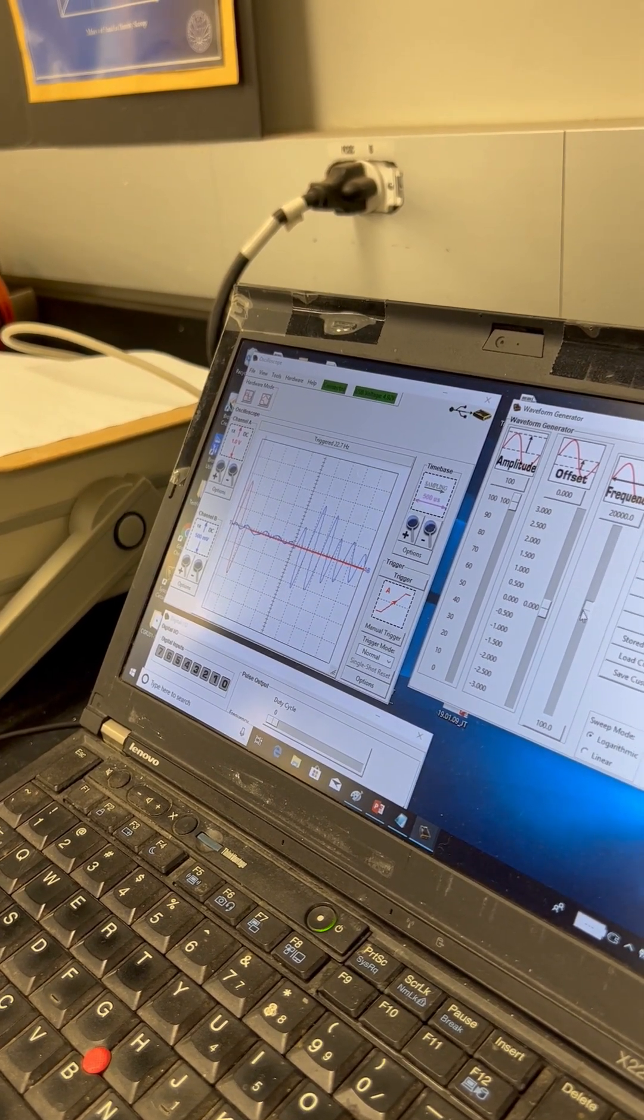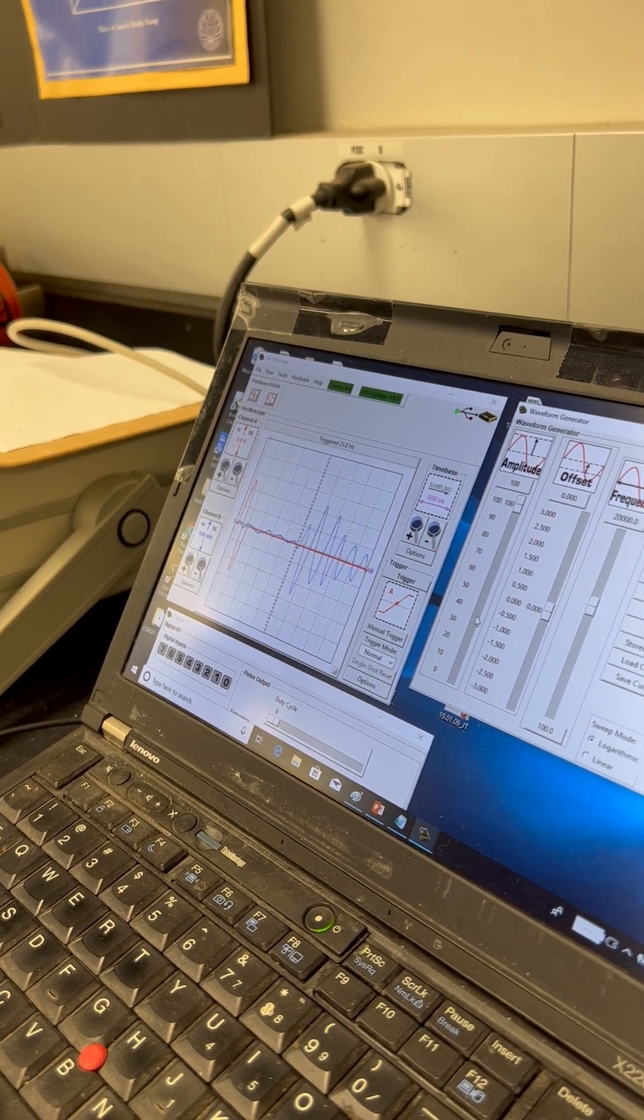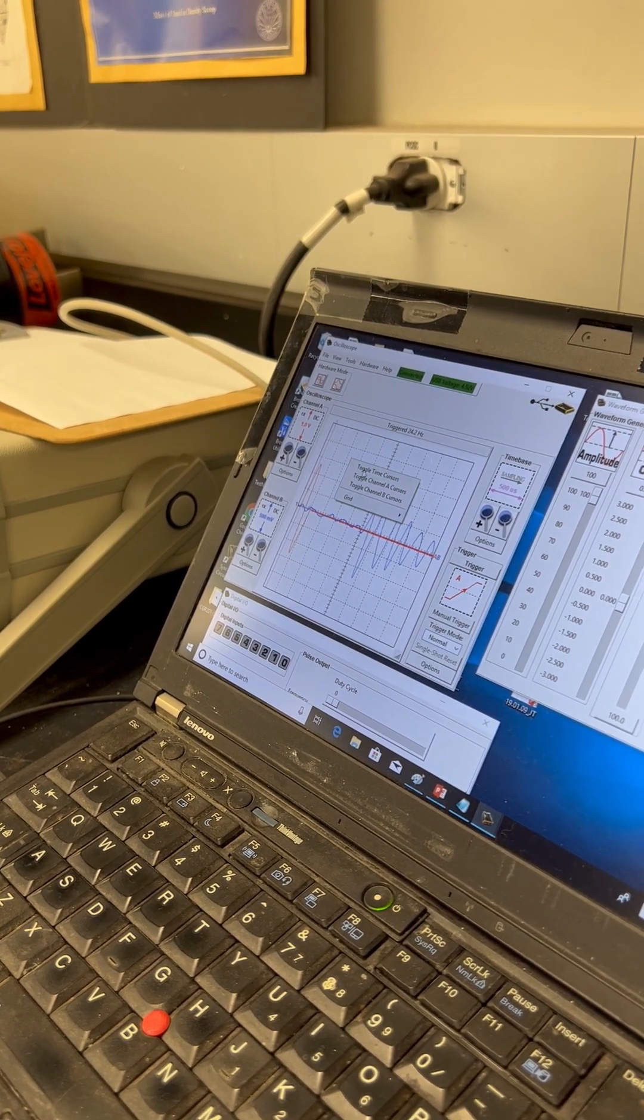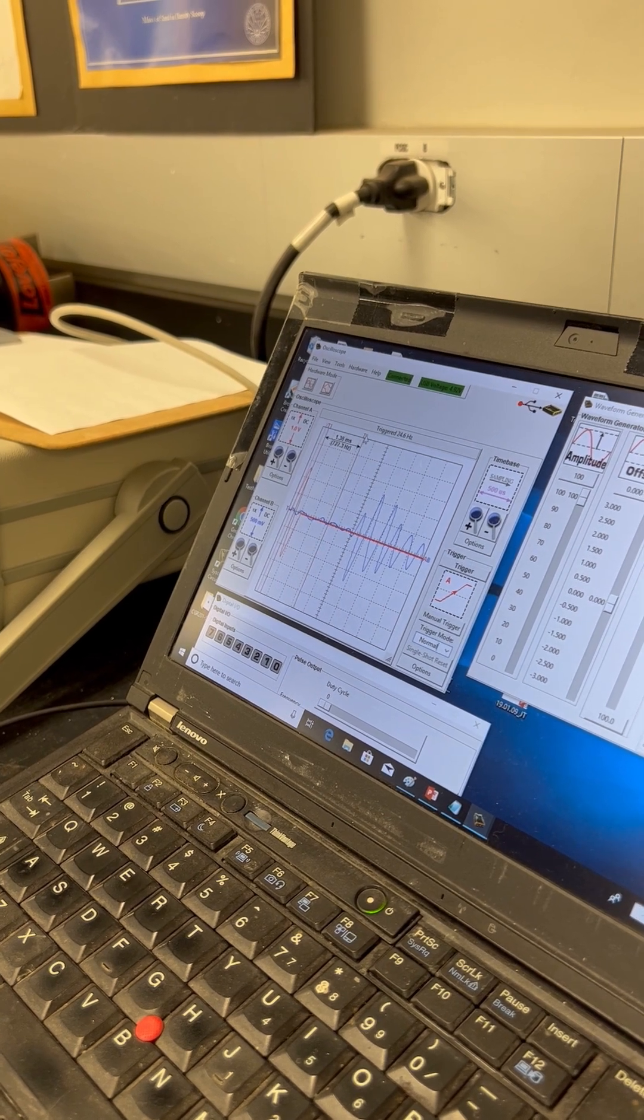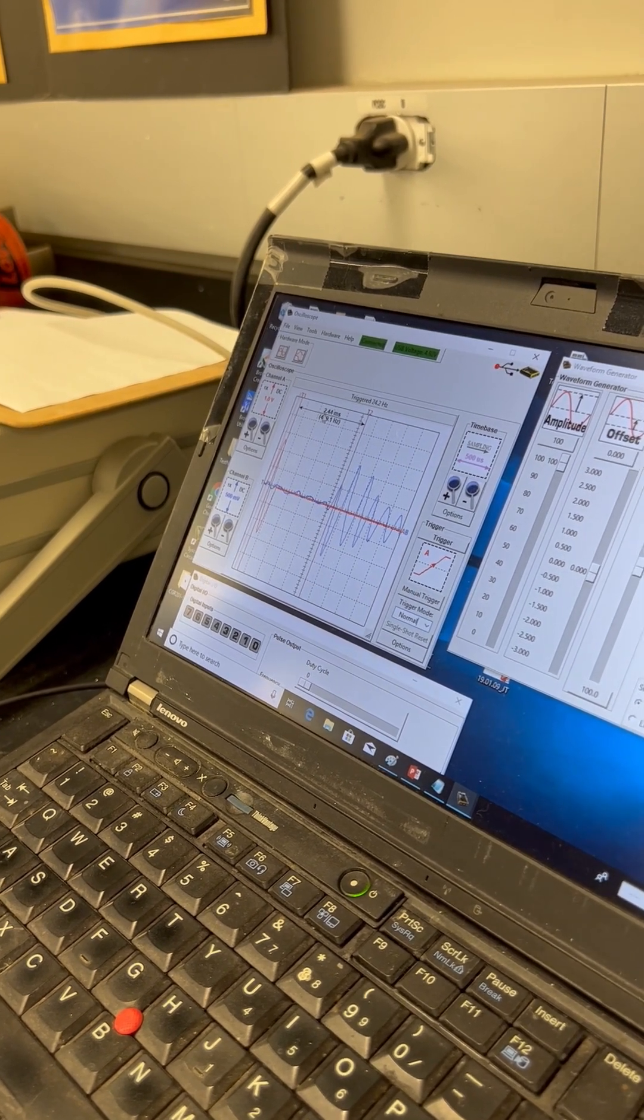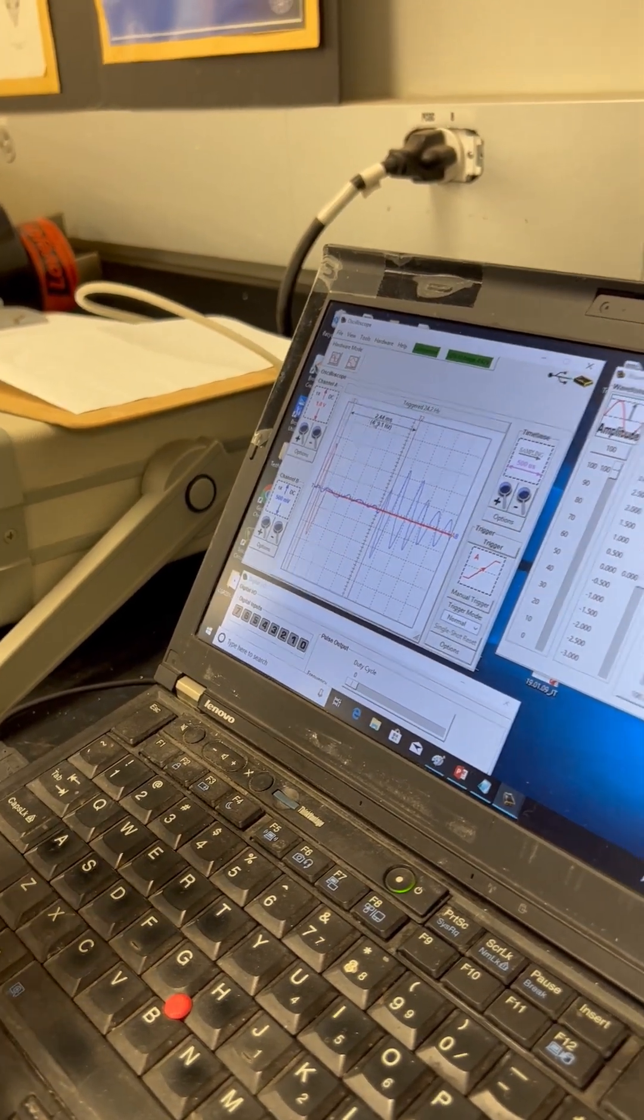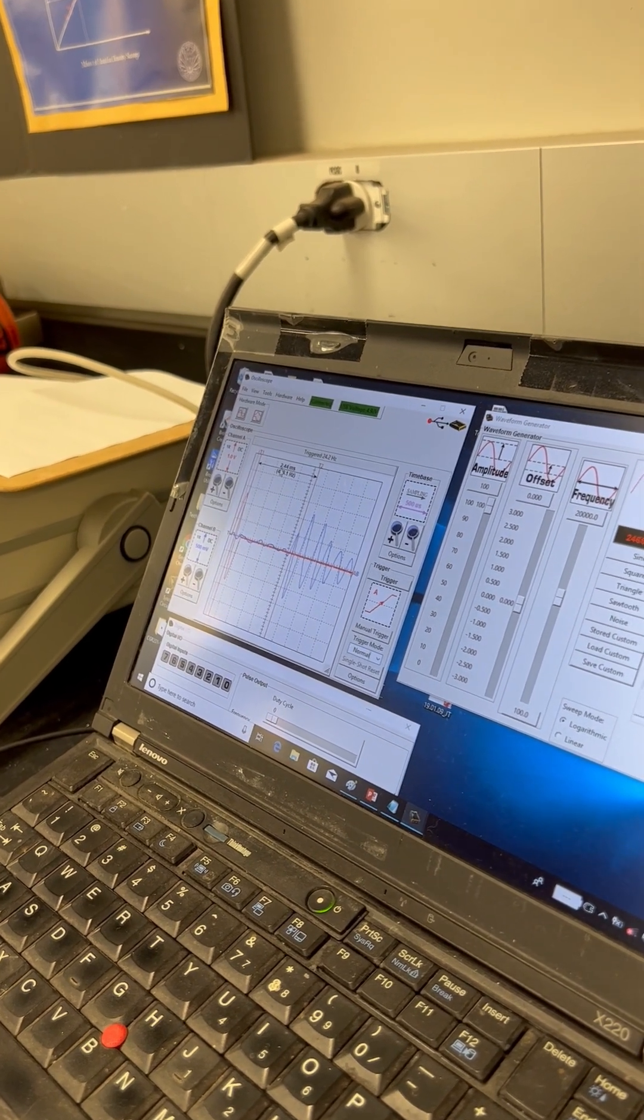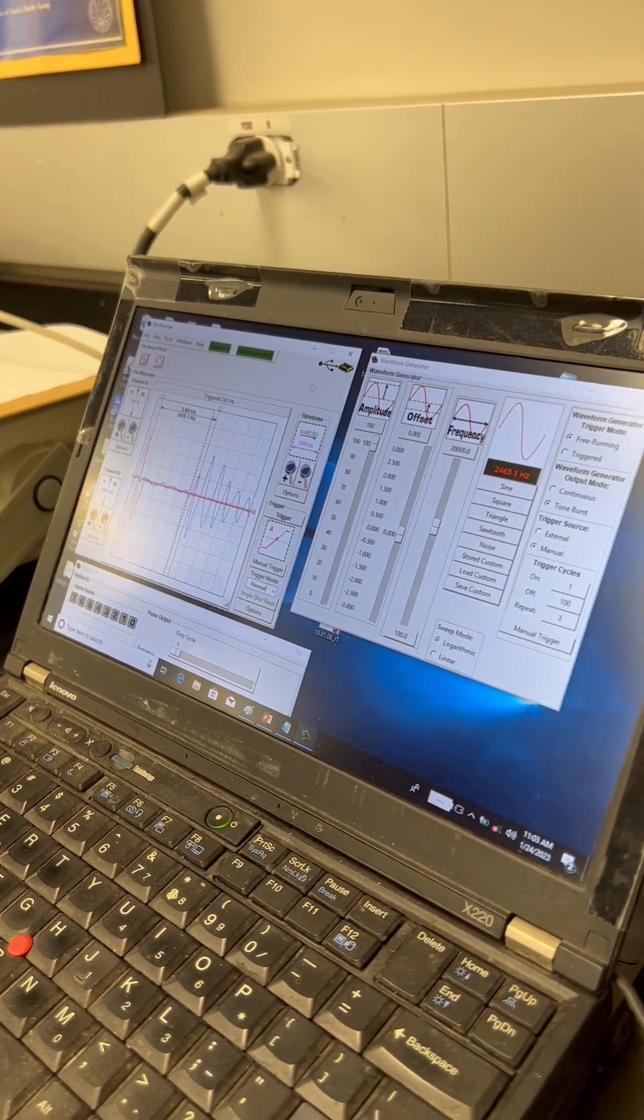And we can also zoom in for the amplitude of the blue signal here. Let's try one more time to see if I can zoom in on the x-axis one more time right there. So now this gives us a pretty good response curve. And if I may, I can fine tune the frequency. So at that point, I call it good on getting one trigger. And then this is the receiver, receiving signal. And now I bring up my time cursor. I label it at T1 here, the peak of the trigger and the peak of the receiving signal. And the time I read here is the time that we want to find out. We want to measure from the trigger bender elements to the receiving bender elements, which is the time difference we're seeing there on the screen. And that travel time can correlate with the shear modulus of the soil specimens, of the soil that we're testing. So this number is very important. And at this point, pretty much we finish the test.